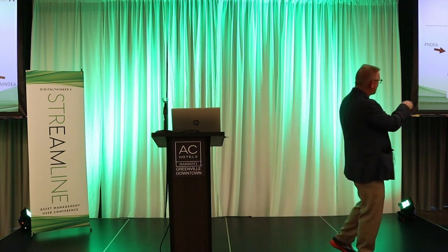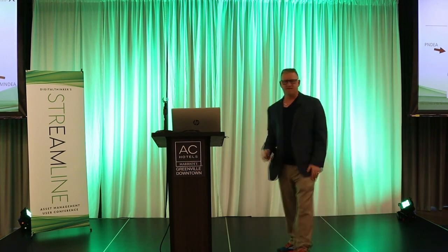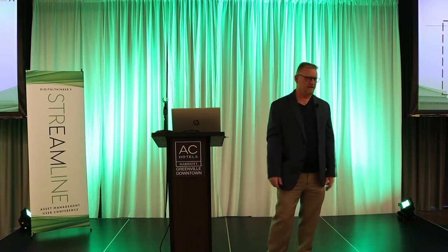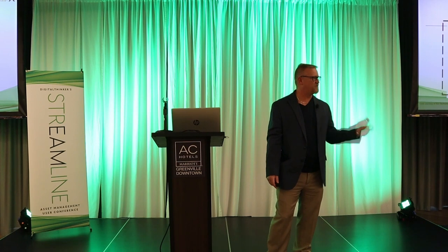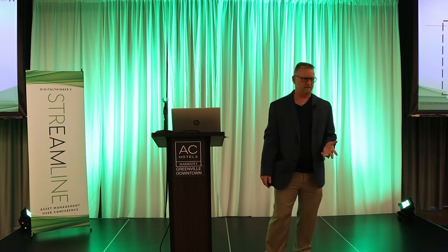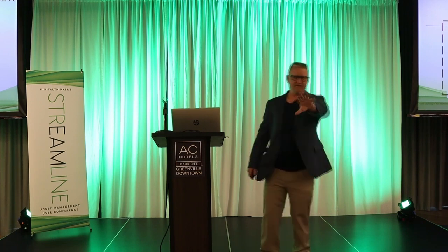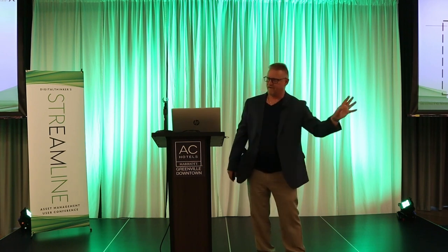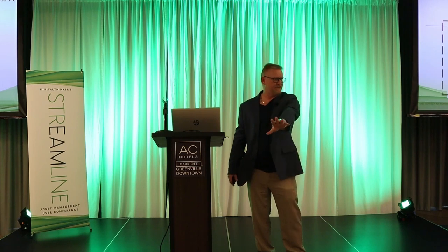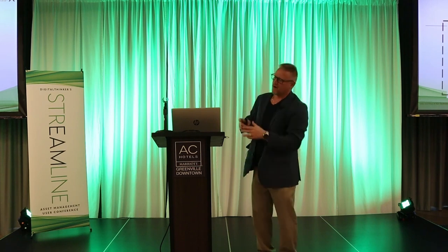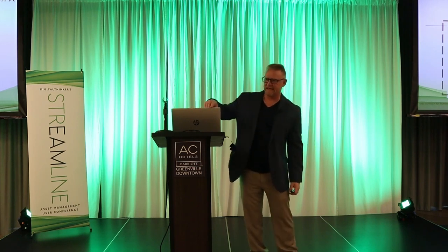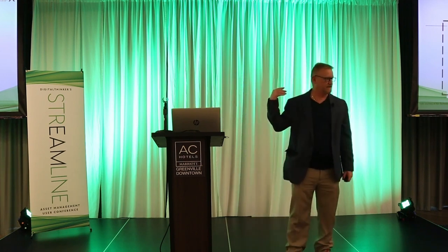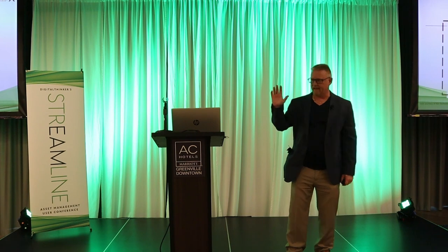So unlike vibration analysis, where you're collecting at various points, motion amplification takes points everywhere. Because what it's looking at is changes in pixel color on a video. So for example, the camera that's in front of me is fixed to the floor. It's not moving, somebody's not holding it where they're shaking, it's fixed. It knows which pixels in that frame are silver or not silver. Does that make sense? Okay.